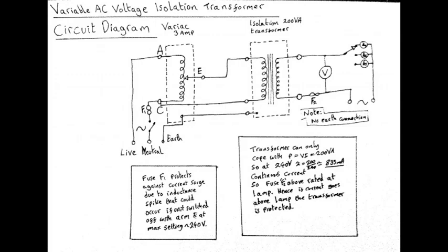So I've included the earth in this setup. The protection earth is connected to a piece of metal on the variac and another piece of metal on the isolation transformer, the lugs, if you like. So I connected those to the lugs. For example, if the live wire was to fall against the lug in the variac, it would just earth out because that's connected directly to earth. Then you'd have a short and it would blow a fuse in the fuse box, as opposed to catching fire. That's what that earth is for.